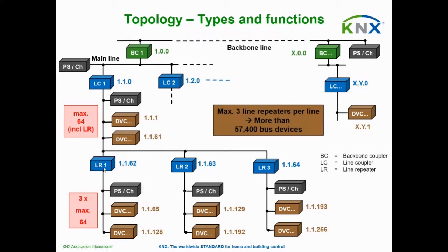Remember, it gives us short circuit protection. So we always need a power supply each side of a line coupler. And it's the same for all of these devices. They are the exact same device as a line coupler. It's just a different configuration, and they're connected in parallel.